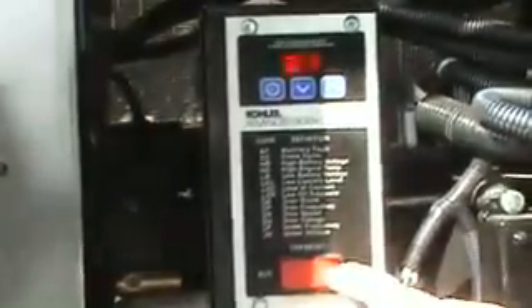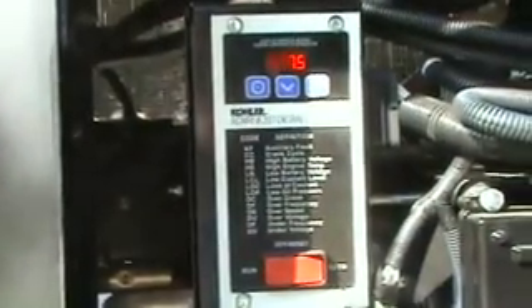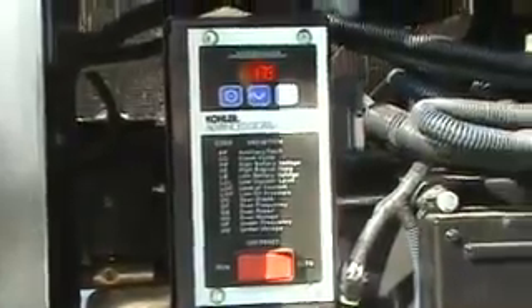Notice it says off-reset. If you have an error code up here, moving it to the middle position, the light goes out, and back to auto resets the error code. If the error code continues to come back, then you're going to need generator service.